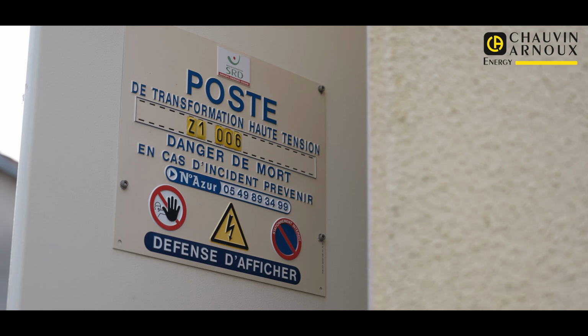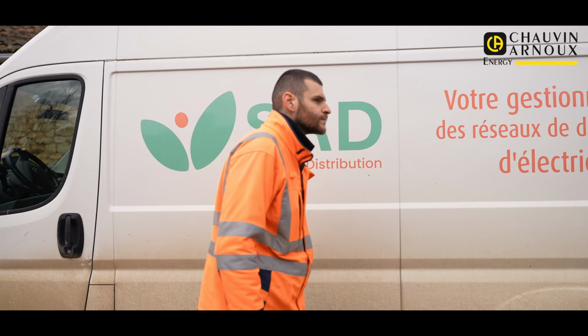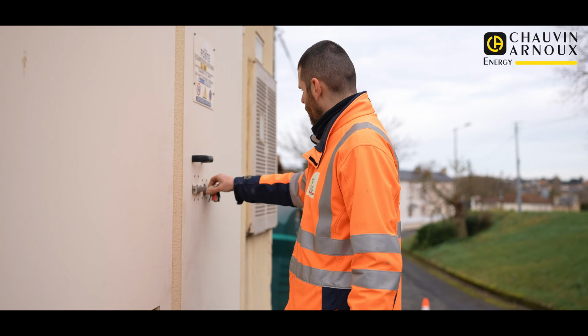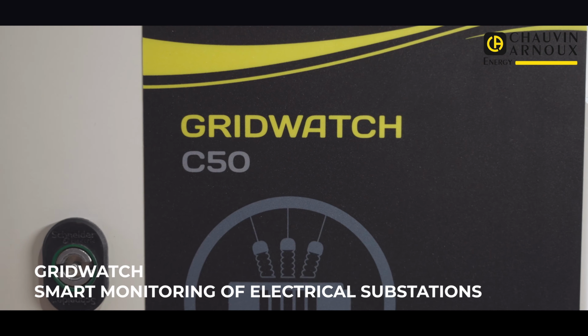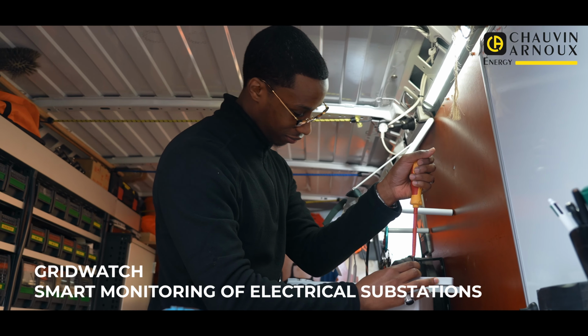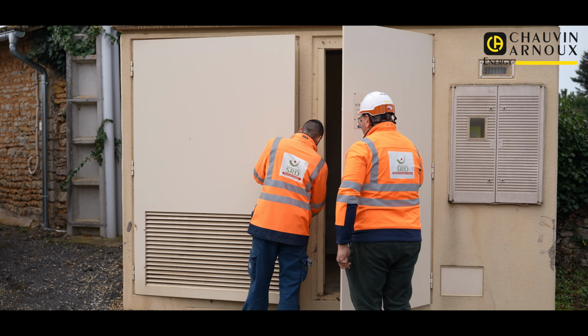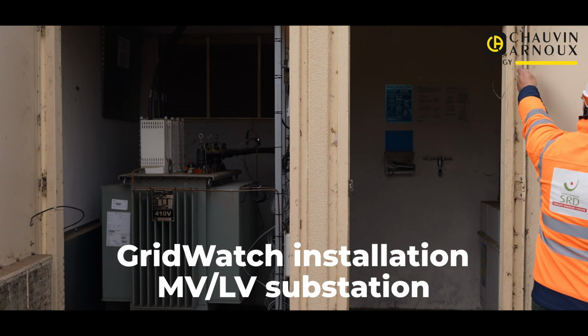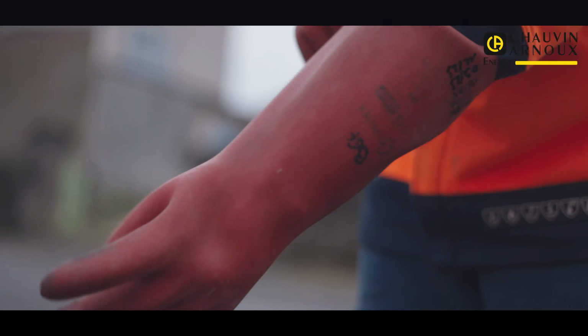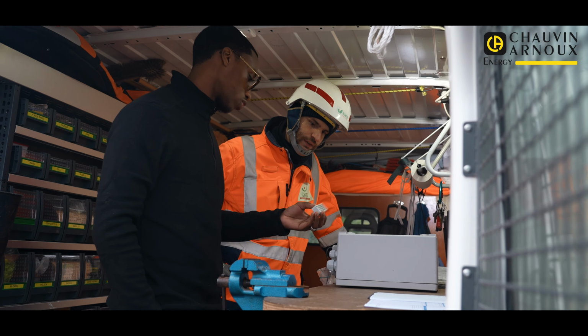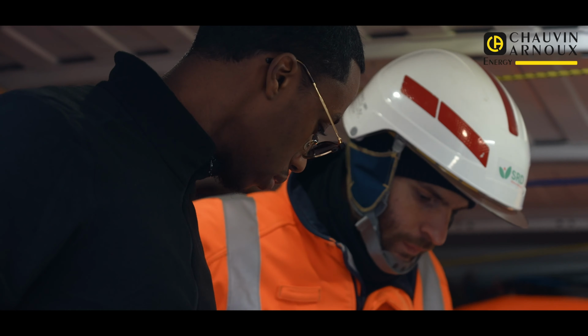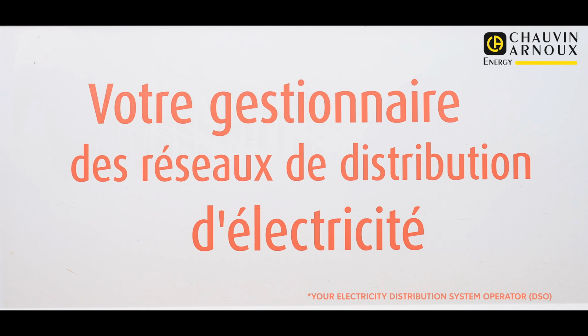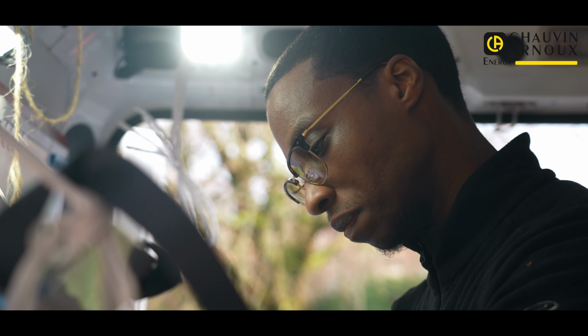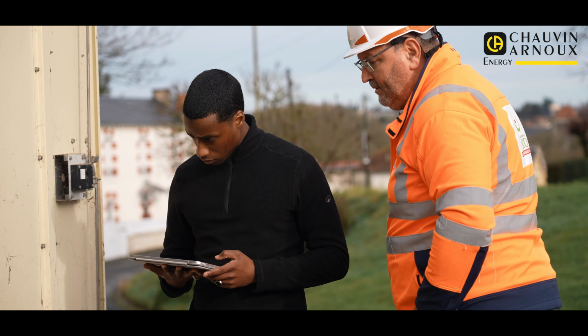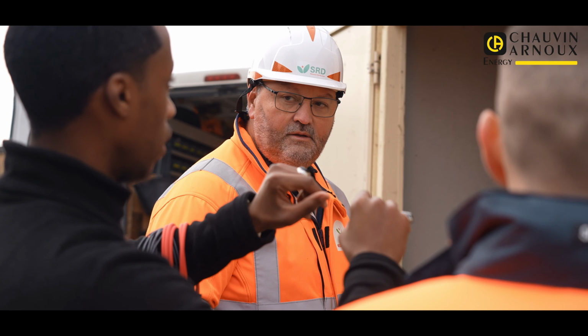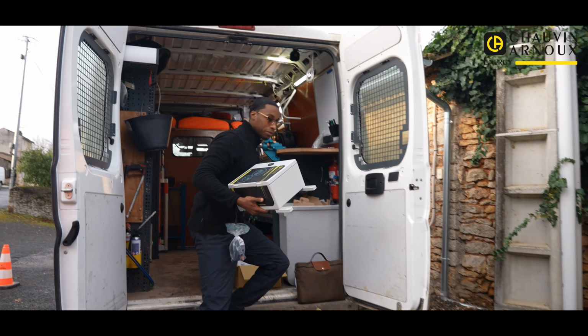To monitor the HV/LV transformer at a substation, our client decided to trial the GridWatch solution from Chauvin Arnoux Energy. Today, we are working in a medium-voltage electrical distribution substation to install a GridWatch unit. The objective is to instrument the transformer and the low-voltage feeders so the distribution network operator can remotely visualize, in real time, all electrical measurements and key environmental parameters.